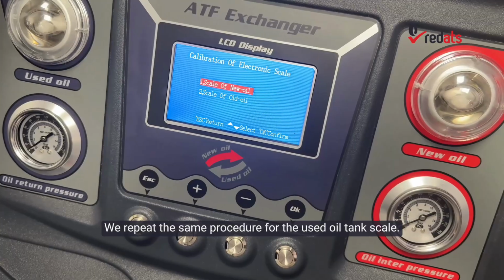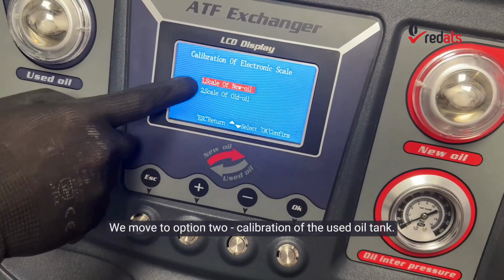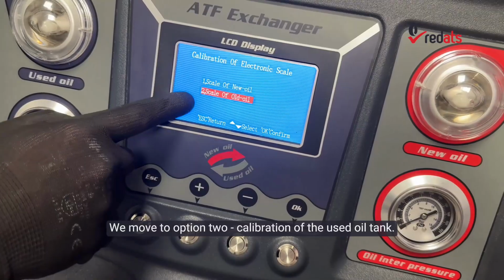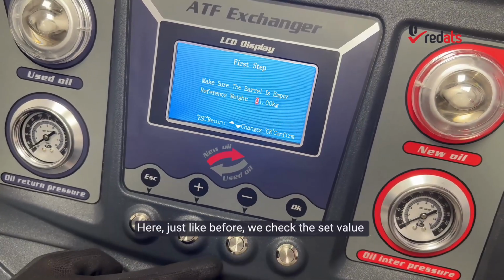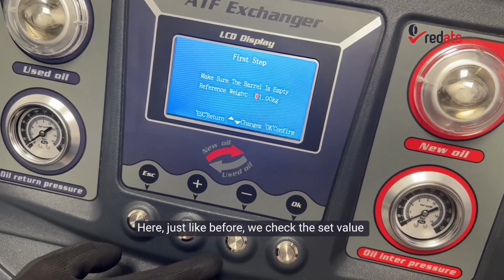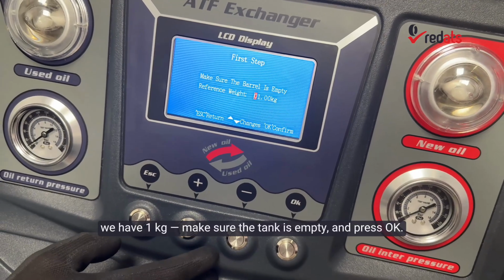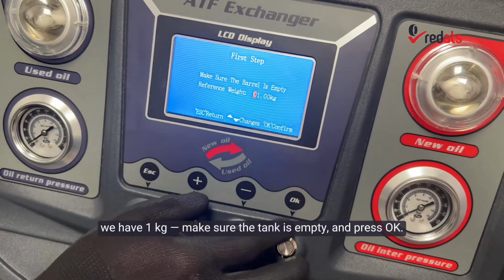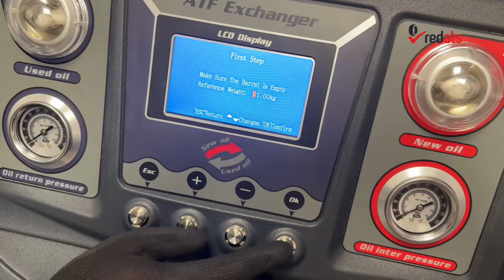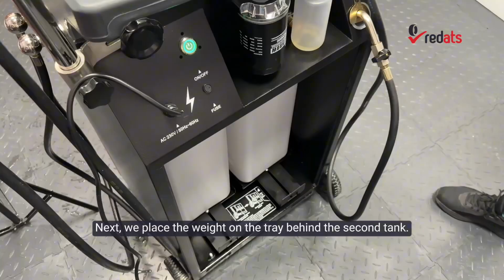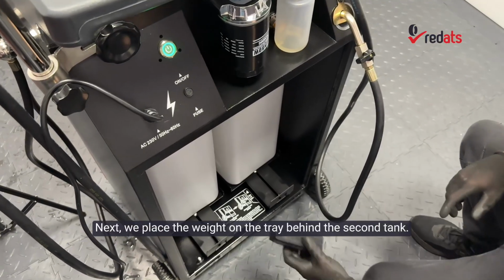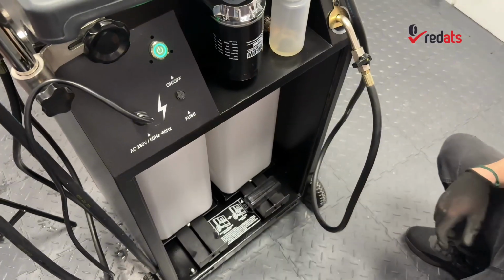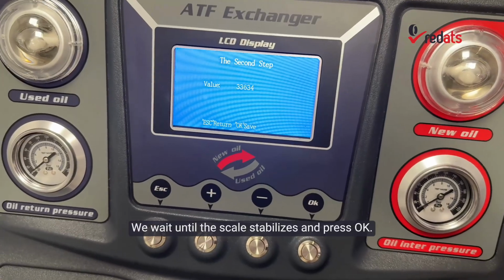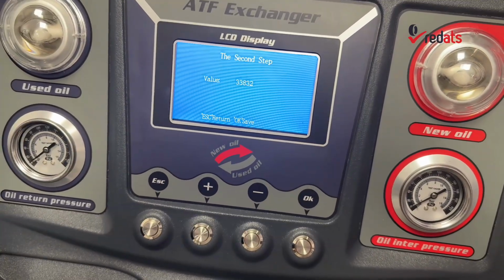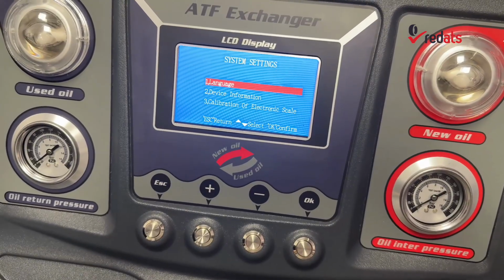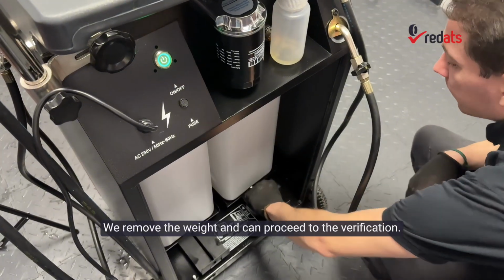We repeat the same procedure for the used oil tank scale. We move to option 2, calibration of the used oil tank. We press OK. Here, just like before, we check the set value. We have 1 kilogram, make sure the tank is empty, and press OK. Next, we place the weight on the tray behind the second tank. We wait until the scale stabilizes and press OK. We remove the weight and can proceed to the verification.